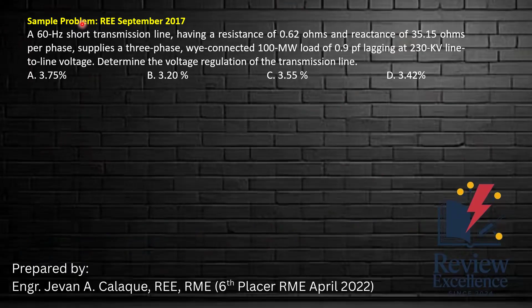We have a problem here, taken from the REE September 2017 board examination. A 60 Hz transmission line having a resistance of 0.62 ohms and reactance of 35.15 ohms per phase supplies a 3-phase Y-connected 100 megawatt load at 0.9 power factor lagging at 230 kilovolts line-to-line voltage. Determine the voltage regulation of the transmission line.